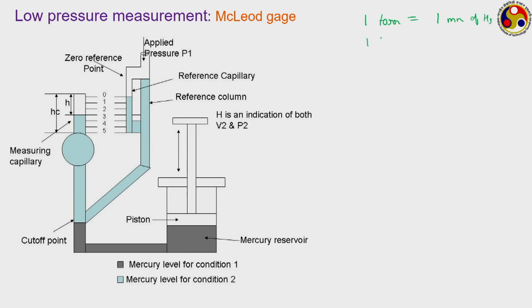So, accordingly 1 Pascal is approximately 7.5 millitorr, thereby giving 1 torr as typically about 133 Pascal. So, 1 torr is a very small value of pressure, and here we are talking about measuring pressures which are of the level of 1 torr or even well below that.